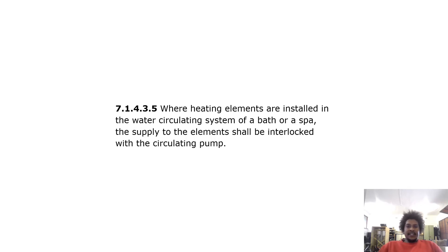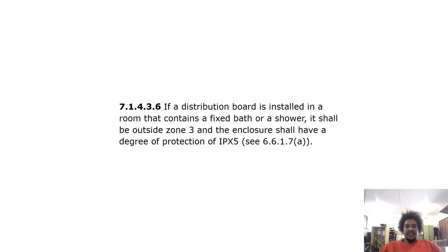Where heating elements are installed in the water circulating system of a bath or spa, the supply to the elements shall be interlocked with a circulating pump. If a distribution board is installed in a room that contains a fixed bath or a shower, it shall be outside zone 3 and the enclosure shall have a degree of protection of IPX5.